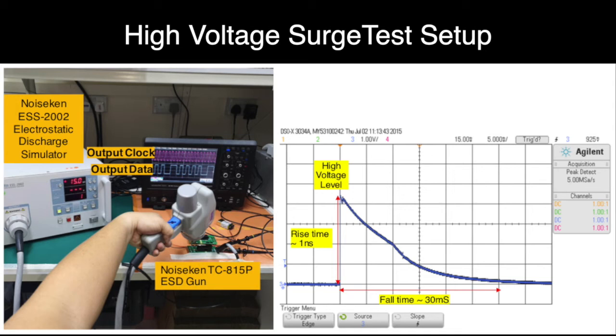A single pulse surge voltage is applied to ground 1 on primary side of the PCB. Since the reference of the ESD gun is connected to ground 2 on secondary side of the PCB, the surge voltage will strike from ground 1 to the isolation structure and then return to ground 2. The surge voltage level is set to begin with 14 kilovolt. The output data of the sigma-delta modulator is monitored on the scope. If the output data continues to switch after the voltage surge, the isolation structure is assumed to be intact. The surge voltage level is then increased by 1 kilovolt. The test will continue at higher voltage levels until the output stops switching, or what we call latch up. Now let's have a look at some live video to give you a better illustration.